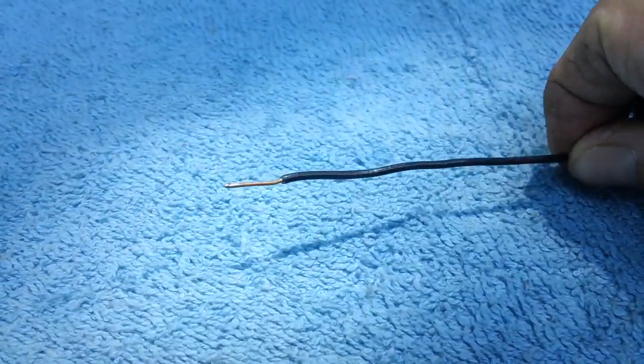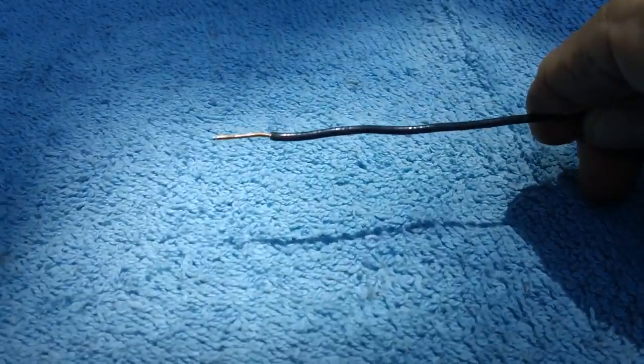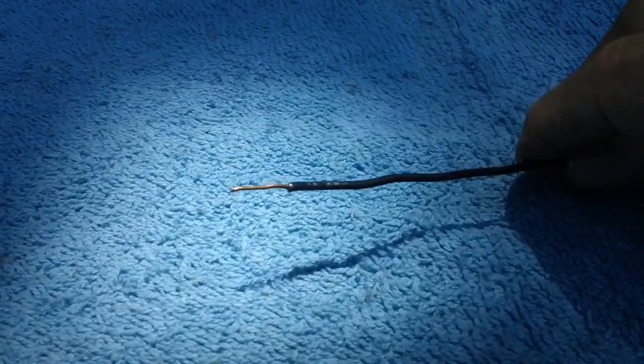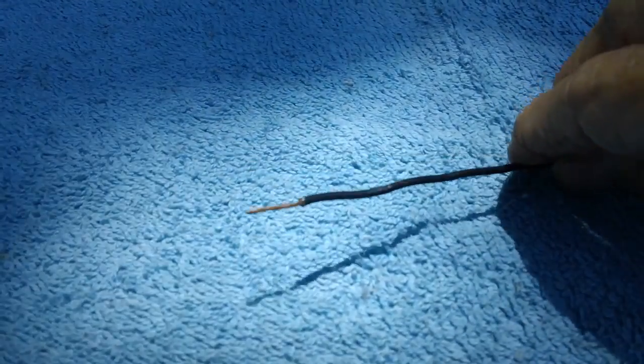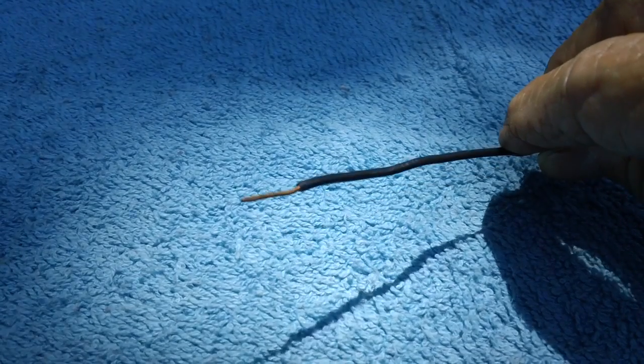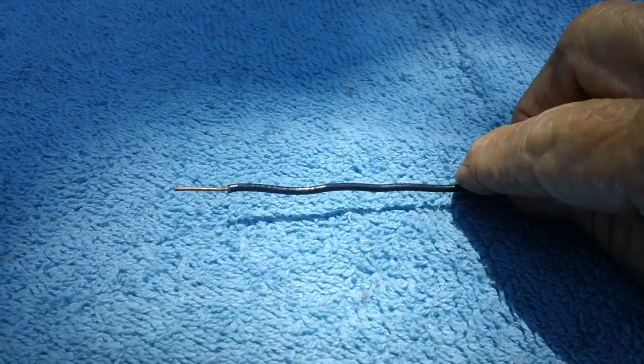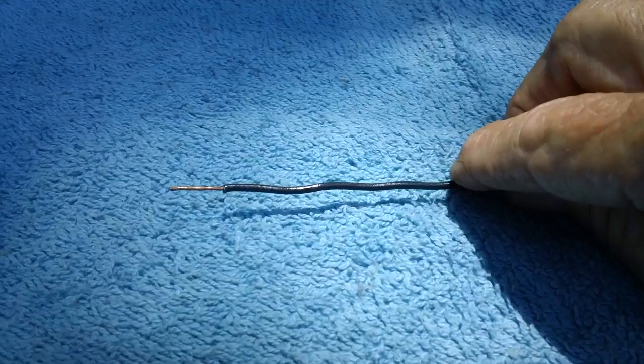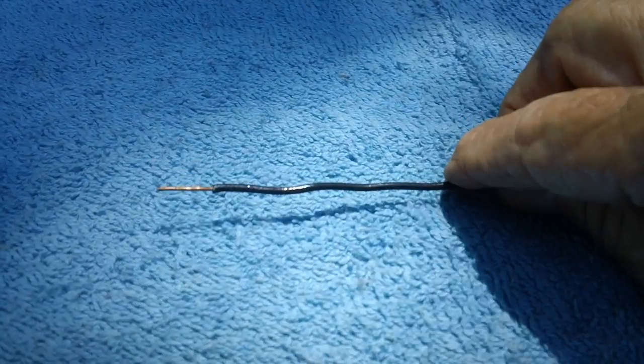But they don't have a current rating on it, and I don't think they even list the voltage rating, which they should. Keep in mind: cross-section of the wire in the center determines current; type of insulation, thickness of insulation, and quality of insulation determine how much voltage it can handle.